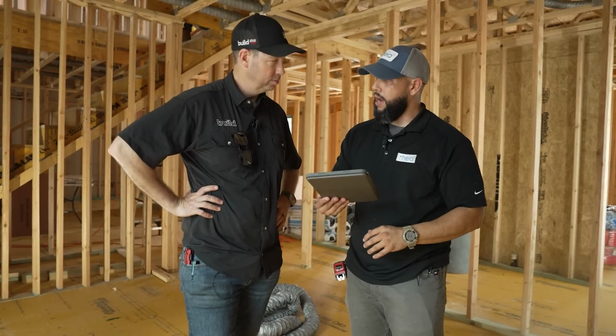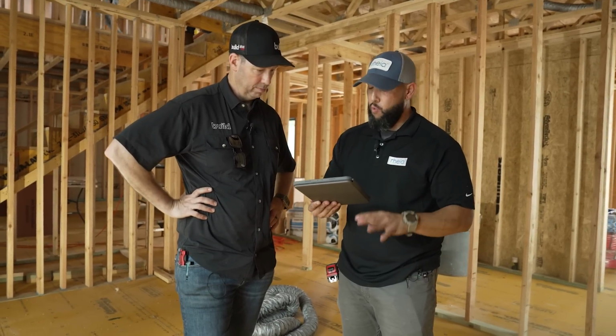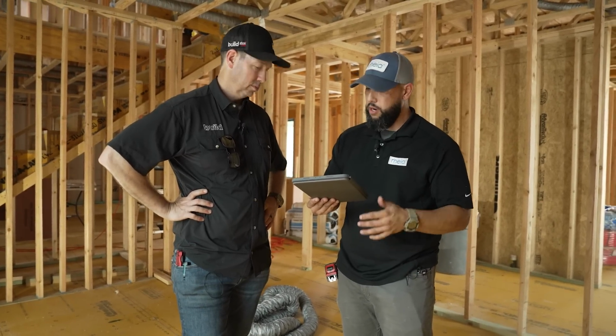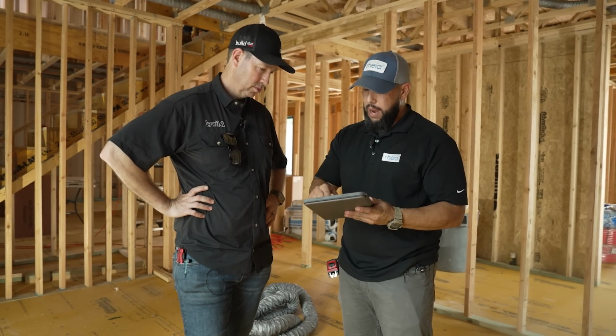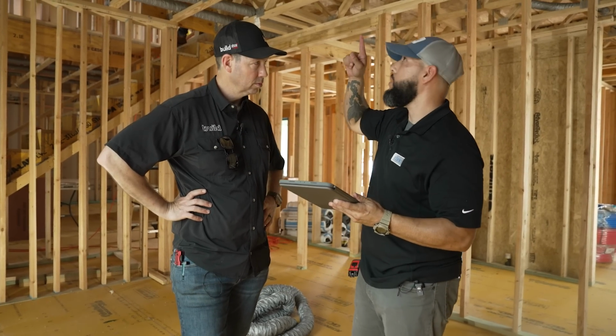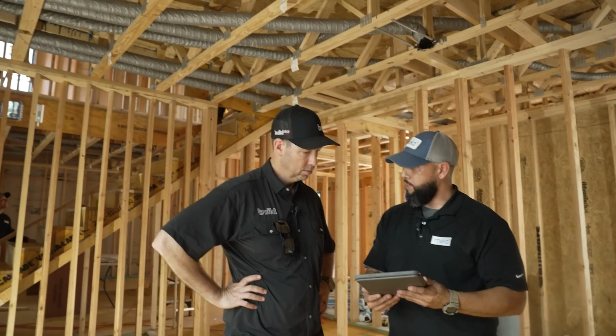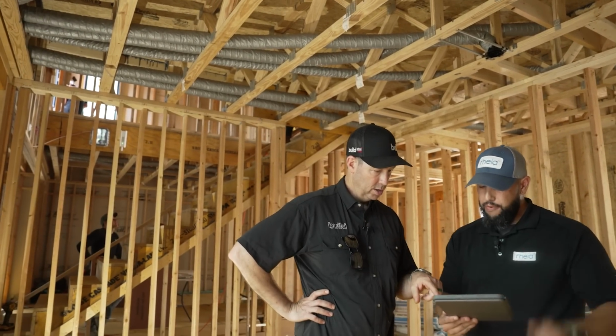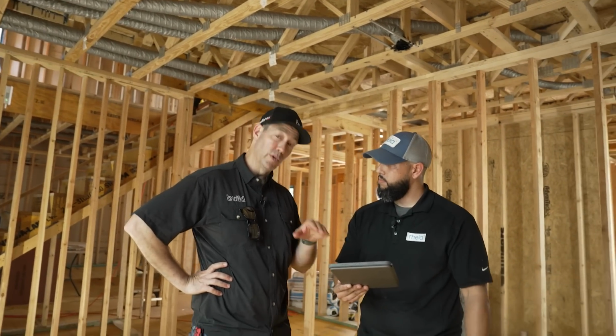So our velocity is not outside of your conventional system. We're not a high pressure system. We're a low pressure, low static system. And the damper position we're expecting to have on these ceiling boots right here is 2 in that position right there. Gotcha. And that's a 38-foot run. And that's expecting to be a 2 with a 38-foot run.